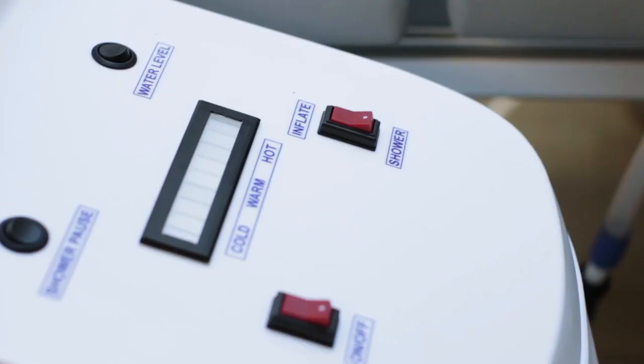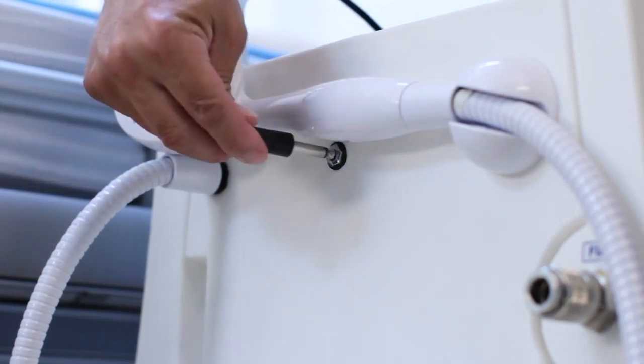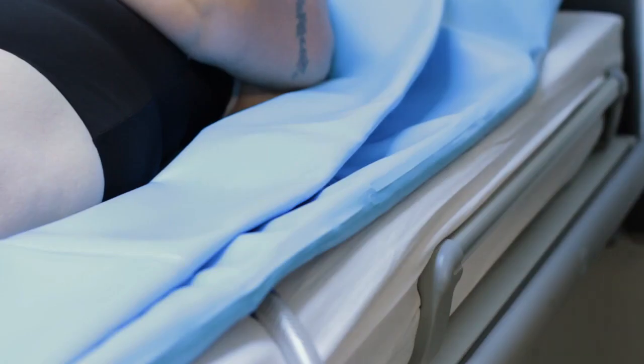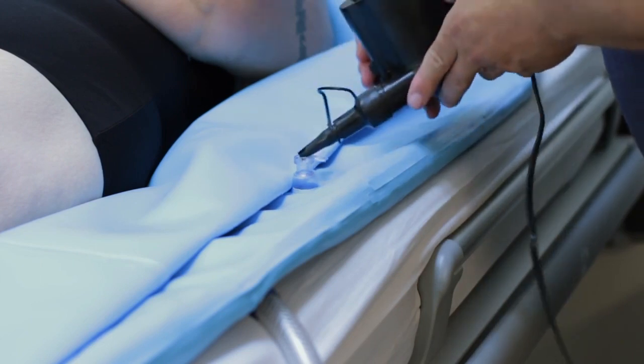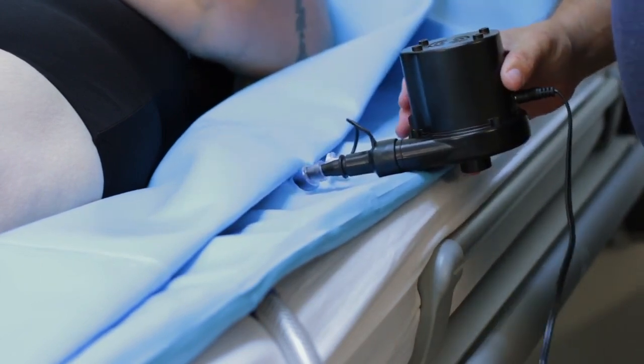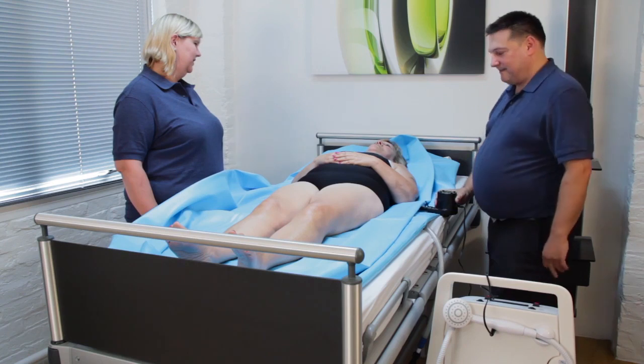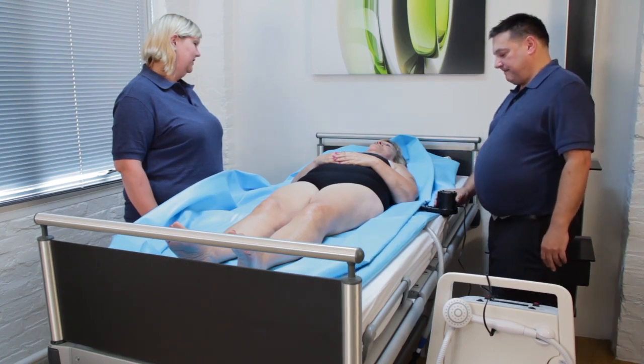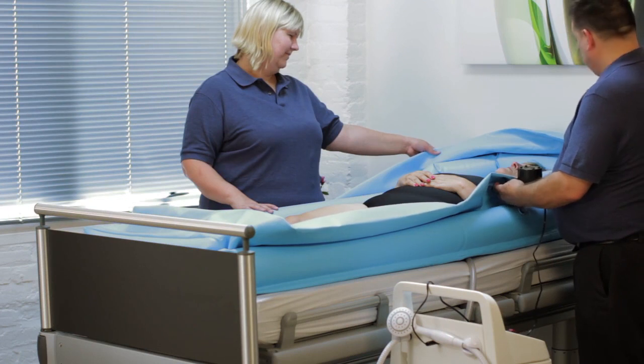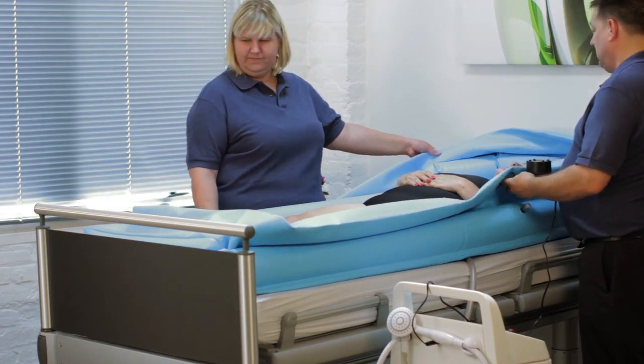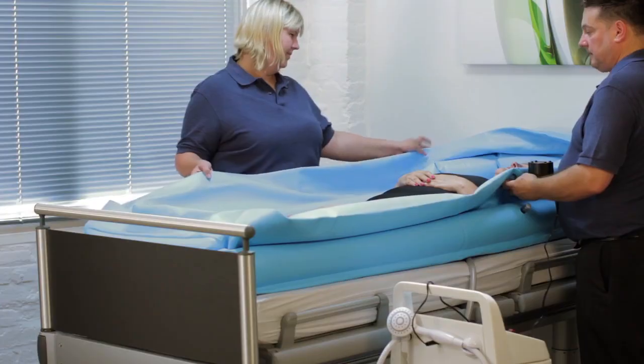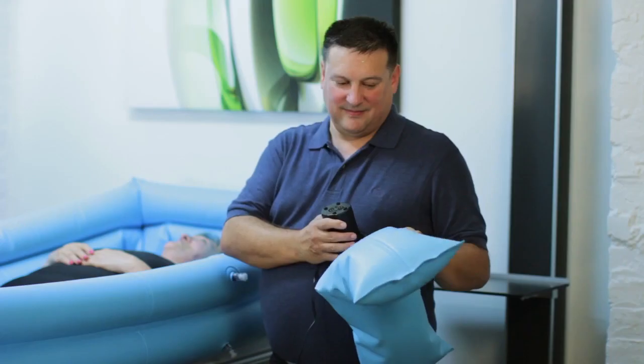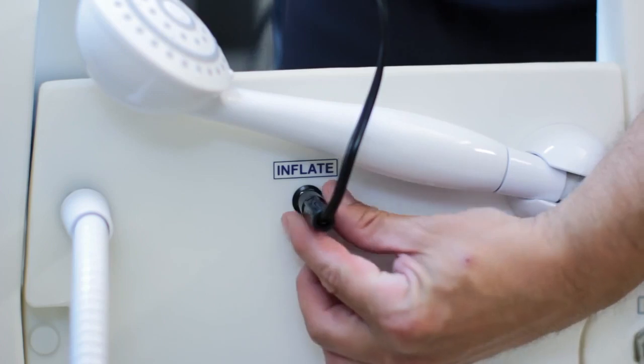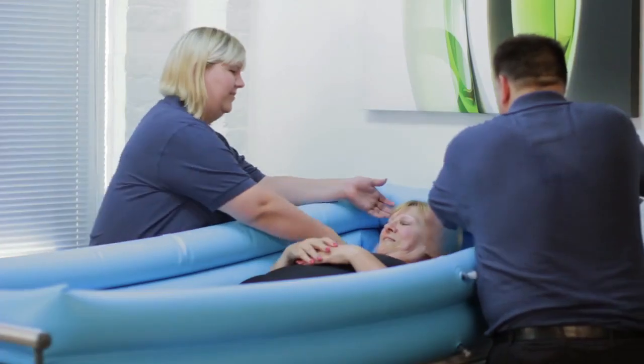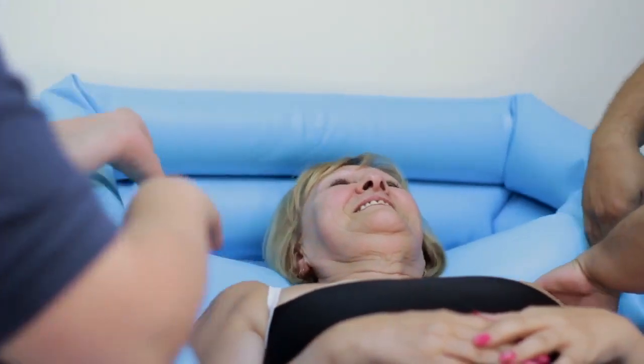Set the switch on the right-hand side of the Water Genie to inflate. Plug in the inflator at the rear of the Water Genie. Place the nozzle of the inflator into the lower of the two inflation valves on the bath. Turn on the inflator's white switch and inflate the lower section. Once inflated, disconnect and insert the inflator into the second valve and inflate the upper section. Inflate the pillow. Then disconnect the inflator completely. Adjust the profile of the bed for the comfort of your patient.